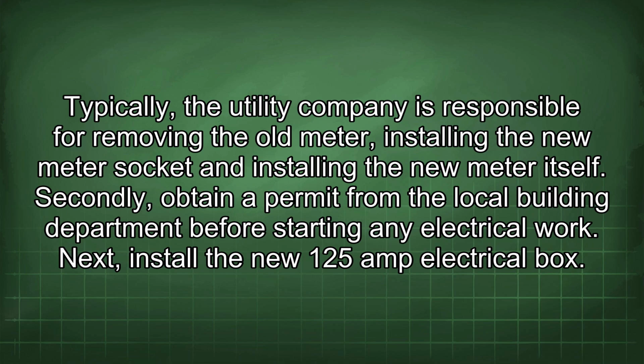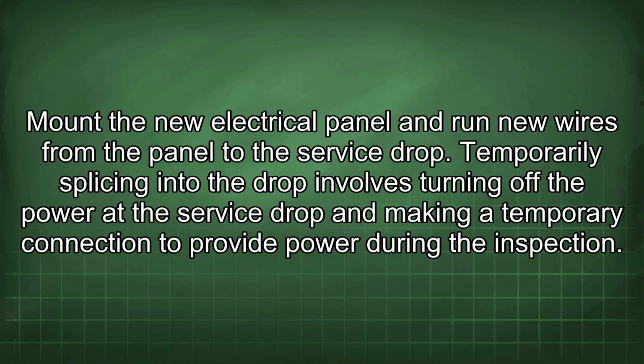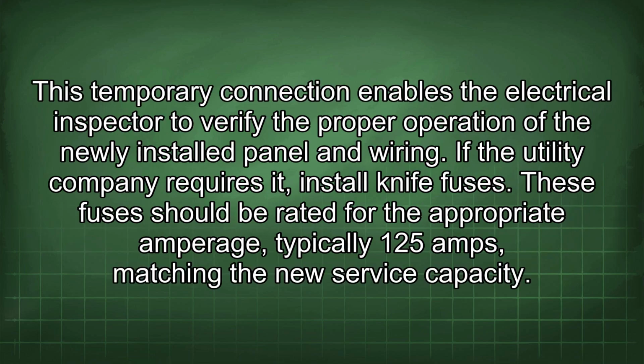Next, install the new 125-amp electrical box. Mount the new electrical panel and run new wires from the panel to the service drop. Temporarily splicing into the drop involves turning off the power at the service drop and making a temporary connection to provide power during the inspection. This temporary connection enables the electrical inspector to verify the proper operation of the newly installed panel and wiring.